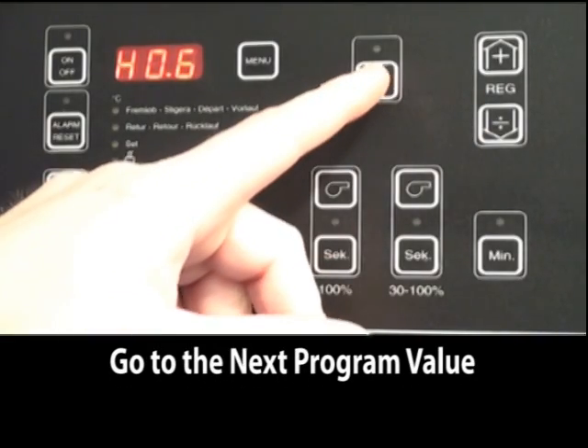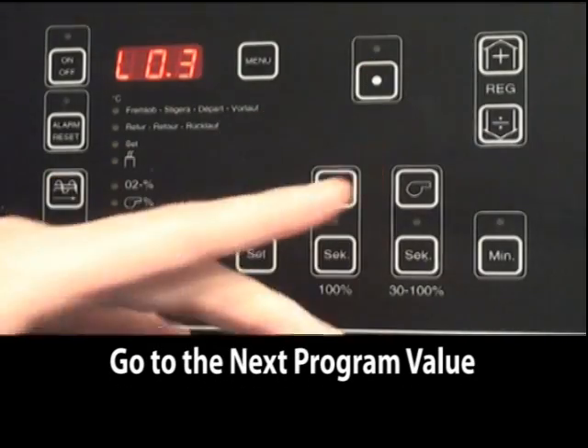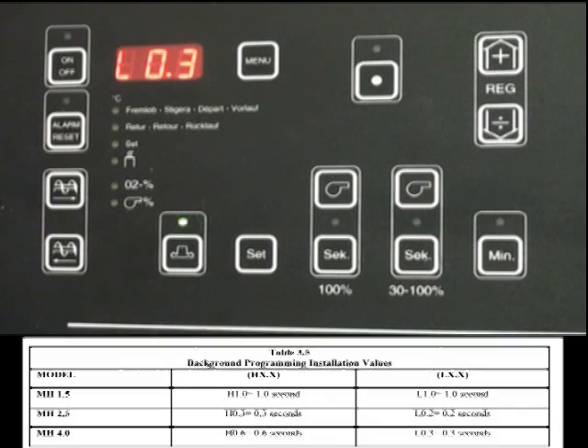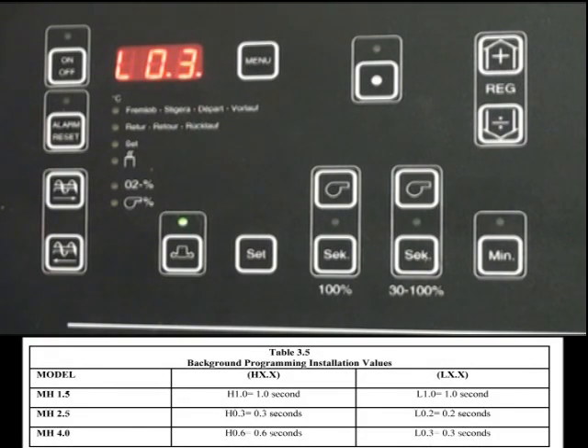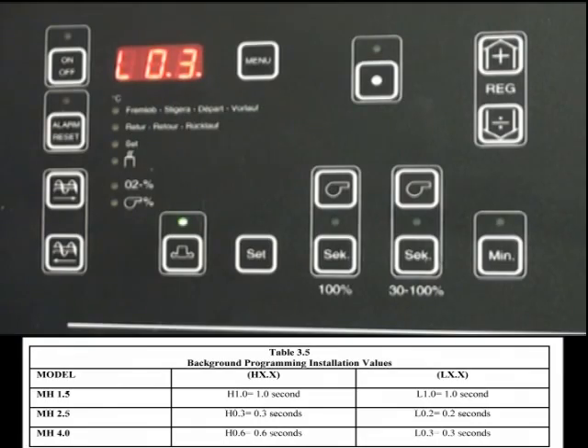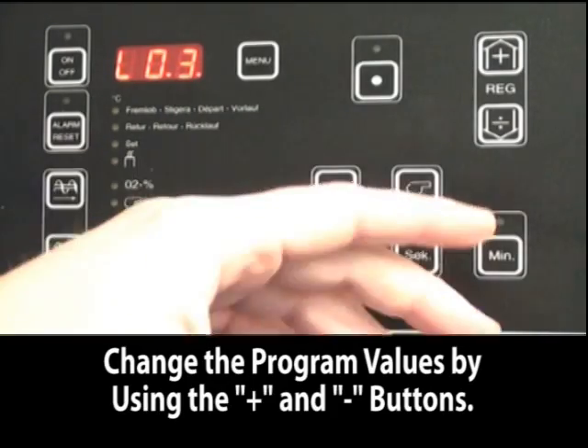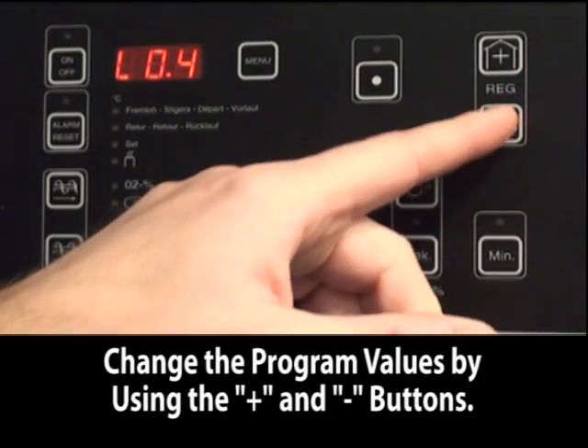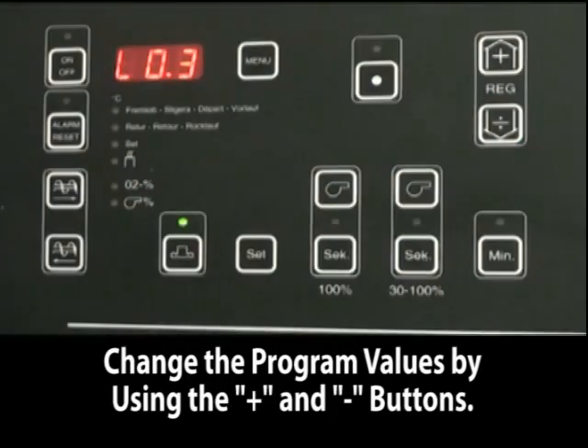The next setting is auger running time in low output mode. This can be either 0.3, 0.2, or 1 seconds depending upon the boiler. You can change the setting by using the plus or the minus buttons.